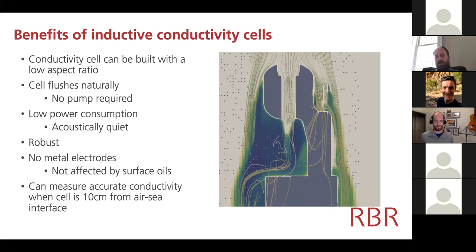The advantage of a low aspect ratio tube is that water just passes through it very naturally. And you can see in this CFD simulation on the right-hand side of the cell advancing through the water column upwards here at about, I think it's 50 centimeters per second in this simulation, that the speed of the water flow, shown by the color, is not degraded in the center of the cell vis-a-vis the speed of the water in the bulk. You can see some boundary effect, of course, around the outside, but we're not measuring significant amounts of conductivity there. The majority of the measurement, over 80% of it, is done in the center. This is a great thing because a cell which naturally flushes means that you measure the seawater without having to do any special efforts to do so.